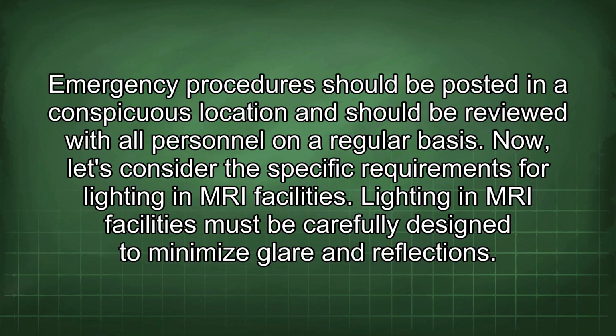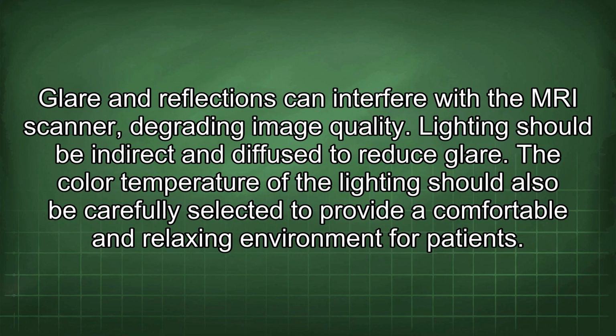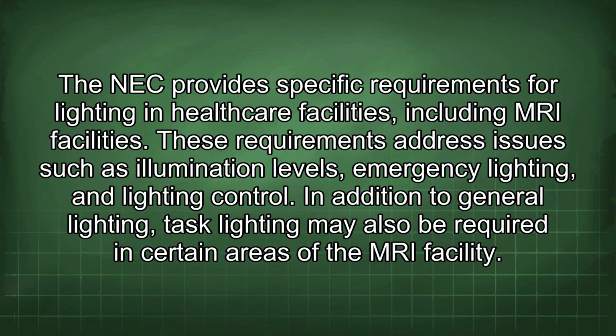Now, let's consider the specific requirements for lighting in MRI facilities. Lighting in MRI facilities must be carefully designed to minimize glare and reflections. Glare and reflections can interfere with the MRI scanner, degrading image quality. Lighting should be indirect and diffuse to reduce glare. The color temperature of the lighting should also be carefully selected to provide a comfortable and relaxing environment for patients. The NEC provides specific requirements for lighting in healthcare facilities, including MRI facilities. These requirements address issues such as illumination levels, emergency lighting, and lighting control.